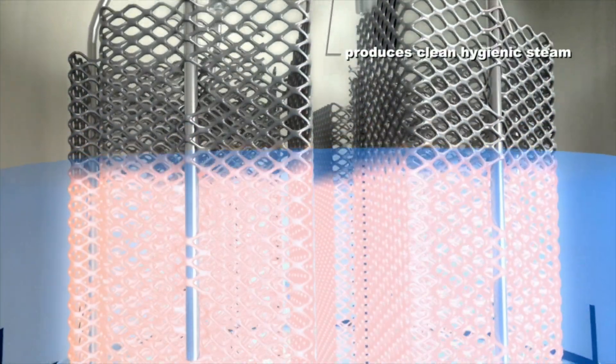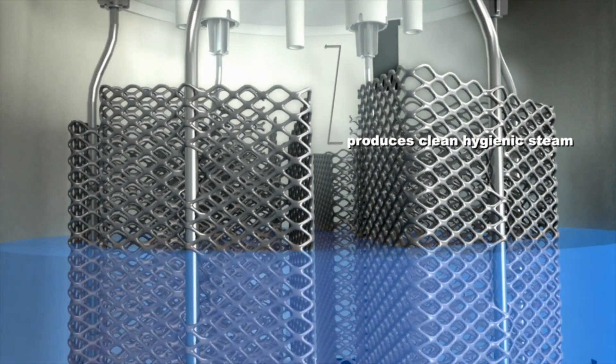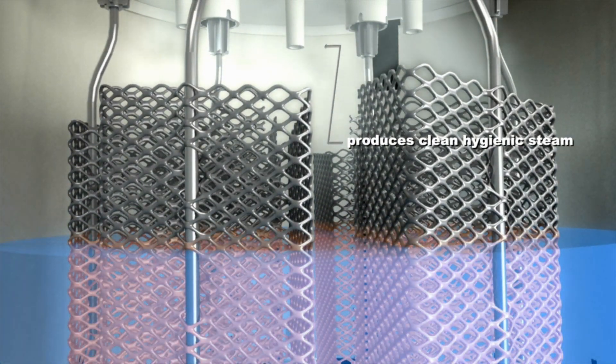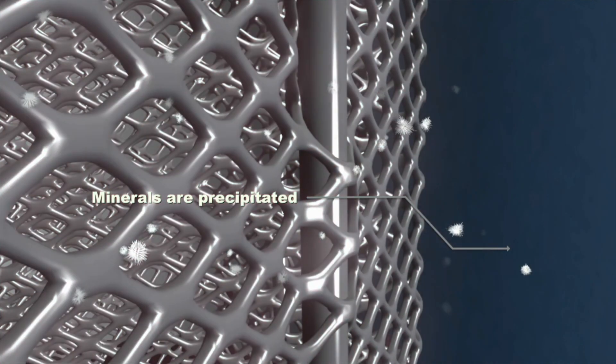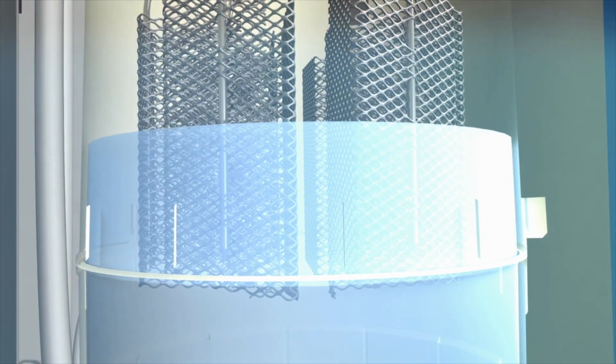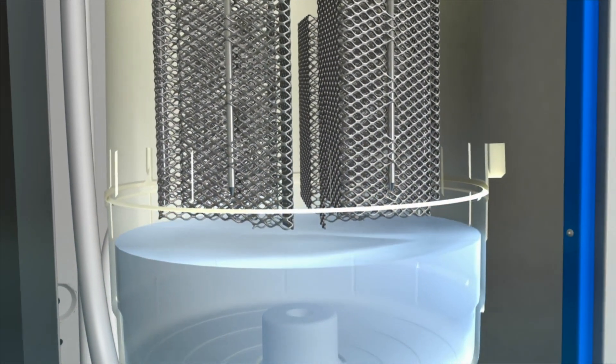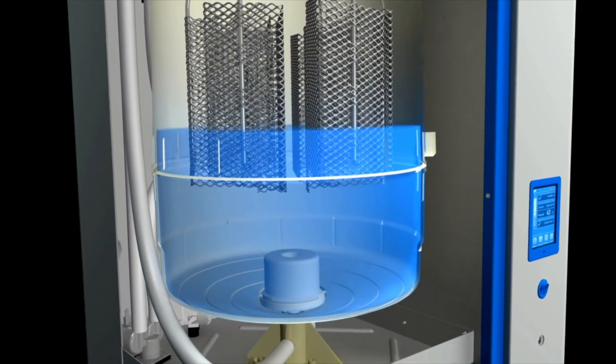The mineral content of the water steadily grows as water evaporates, increasing its conductivity. The mineral concentration must be reduced. This is achieved by rapidly replacing high mineral content water with fresh water to maintain consistent steam output.